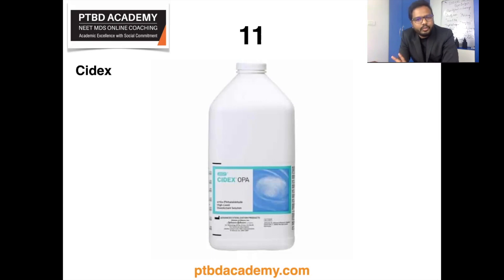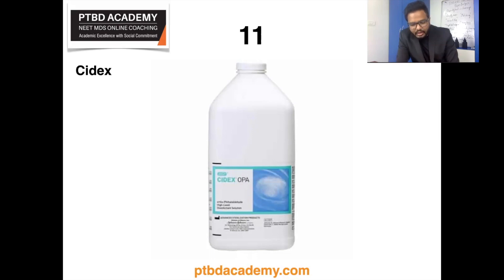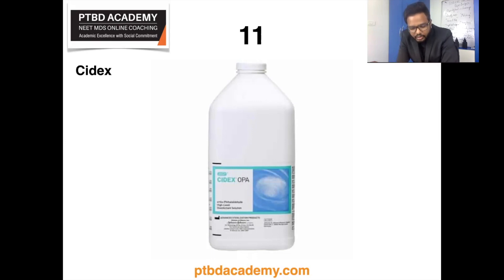It is commonly used to sterilize instruments in between cases where we use four trays: one tray for keeping Cidex solution and the other three trays for sterile water. Sharp instruments are to be kept in activated solution of Cidex for 15 minutes and then washed three times in sterile water kept in those three trays.